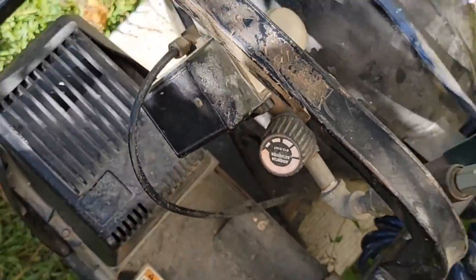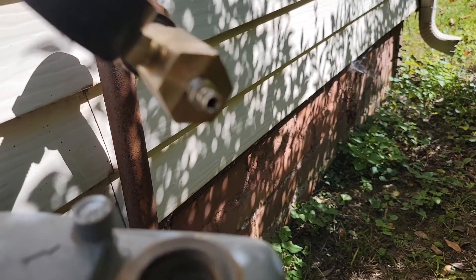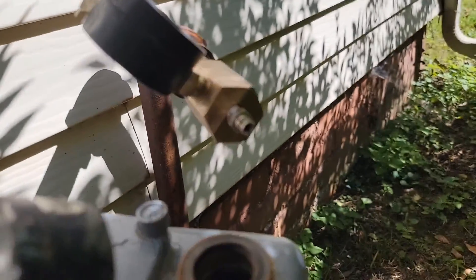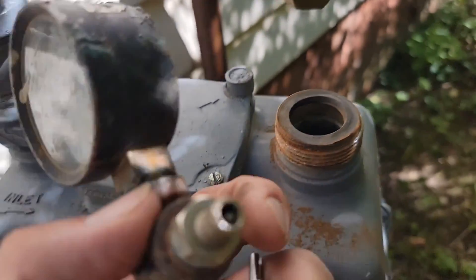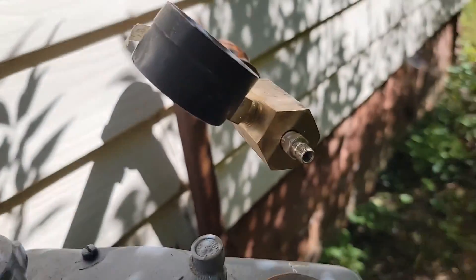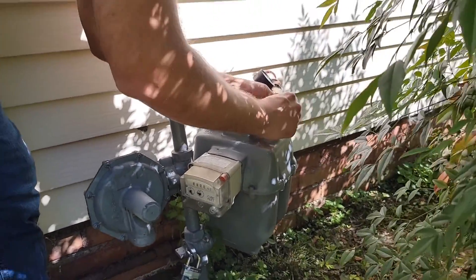Time for pressure. Attempt number one has been a failure because there's no stem — I need to check that and make sure I have a valve core in there before I pressure it up. So I'm going to take this one out and put the correct one in. Definitely need that.